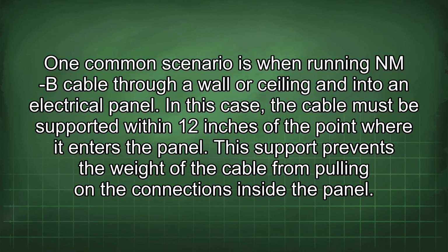One common scenario is when running NMB cable through a wall or ceiling and into an electrical panel. In this case, the cable must be supported within 12 inches of the point where it enters the panel. This support prevents the weight of the cable from pulling on the connections inside the panel.